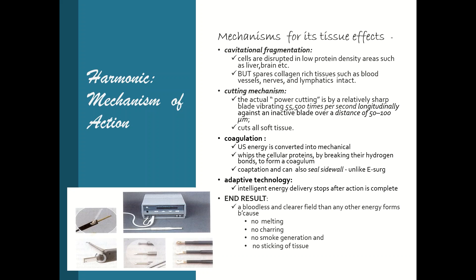The cutting mechanism uses a sharp blade vibrating at 55,000 to 55,500 times per second longitudinally, moving a distance of about 80 micrometers (range 50 to 100 micrometers), cutting all tissues. It also has a coagulation effect: ultrasound energy is converted into mechanical energy, whipping cellular proteins by breaking their hydrogen bonds to form a coagulum. Coaptation can also seal the vessel wall — an advantage over electrosurgery, which requires grasping both walls before sealing.